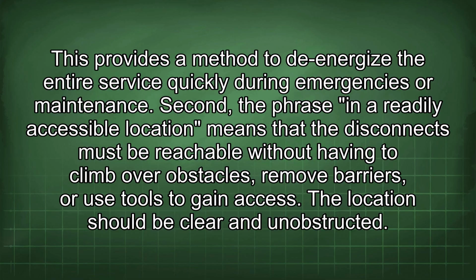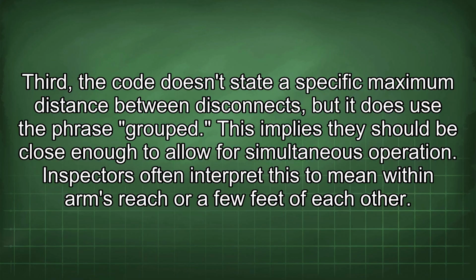Second, the phrase "in a readily accessible location" means that the disconnects must be reachable without having to climb over obstacles, remove barriers, or use tools to gain access. The location should be clear and unobstructed. Third, the code doesn't state a specific maximum distance between disconnects, but it does use the phrase "grouped." This implies they should be close enough to allow for simultaneous operation.